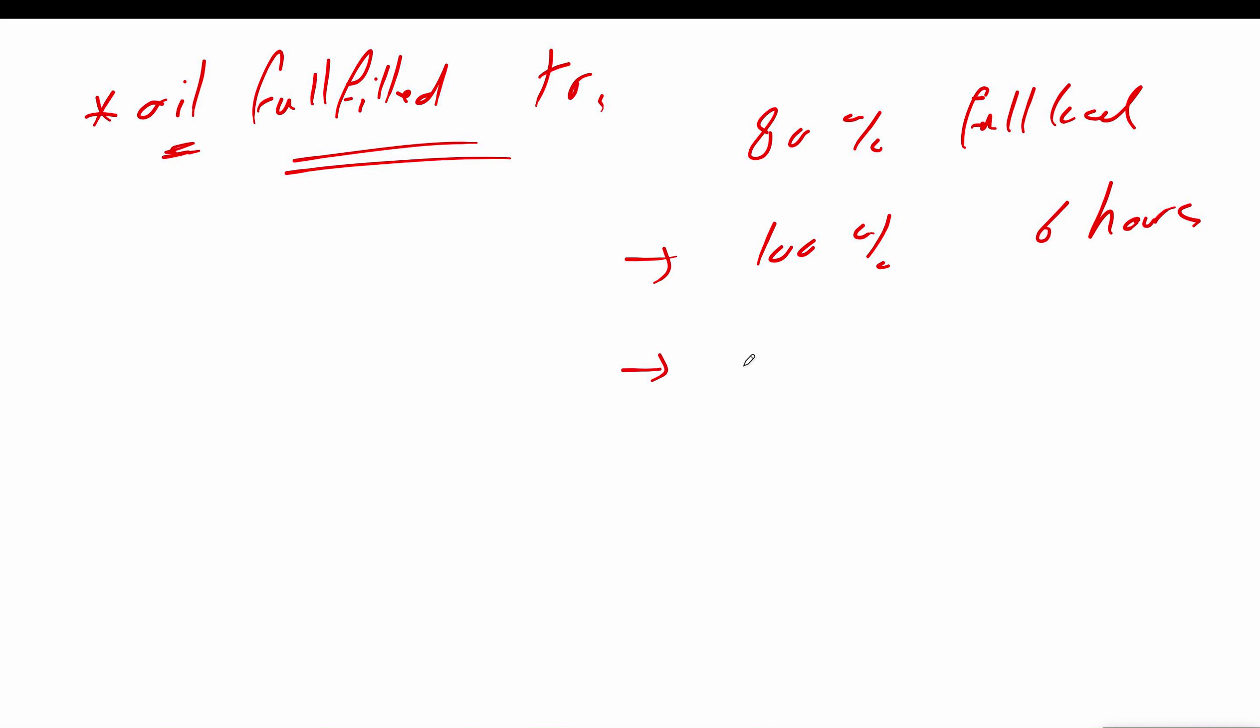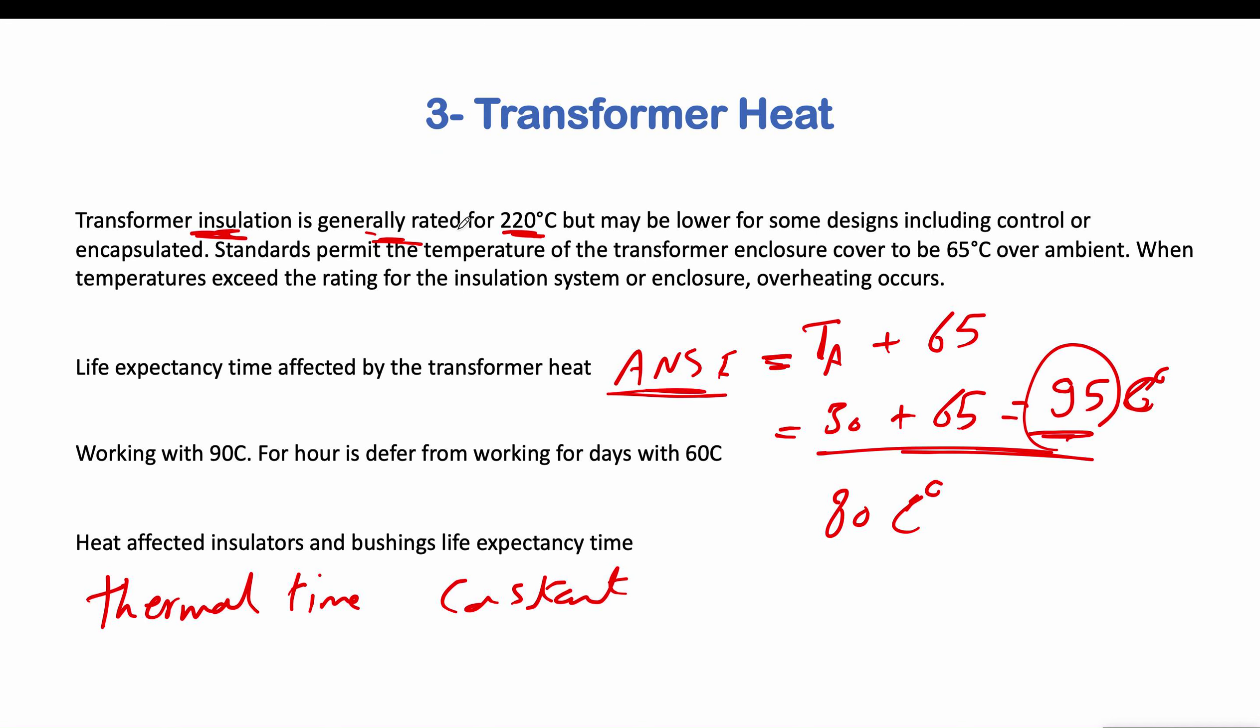And they can stand up with 110 percent for maybe four hours. And it can stand up with 120 percent for one hour. And this overload in which the transformer can stand up with is a consequence of a high thermal time constant of oil transformers.